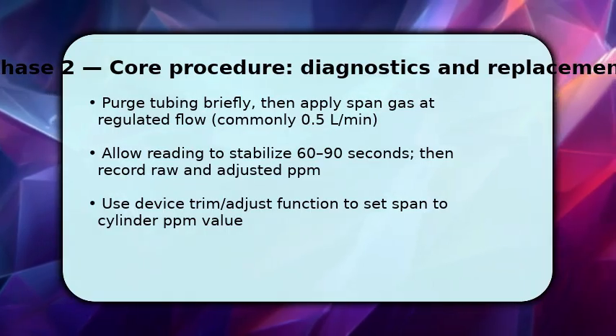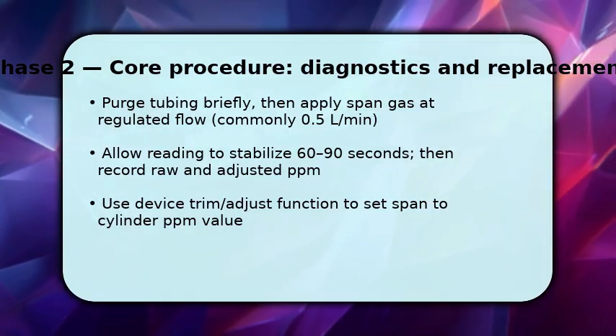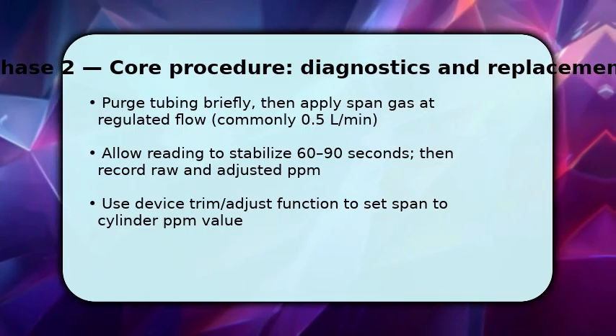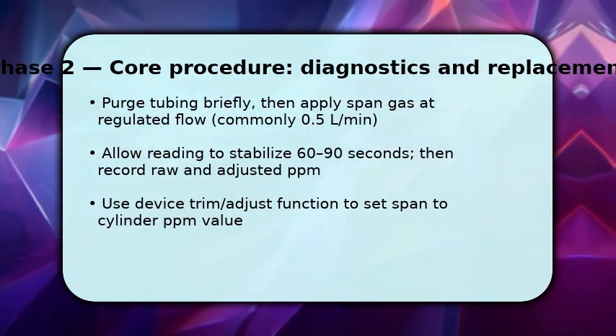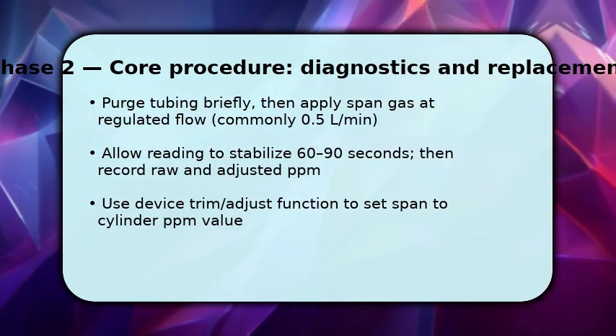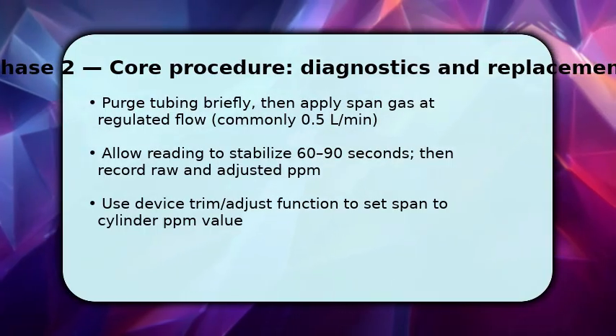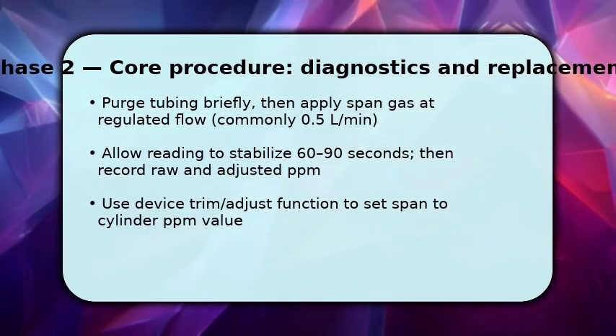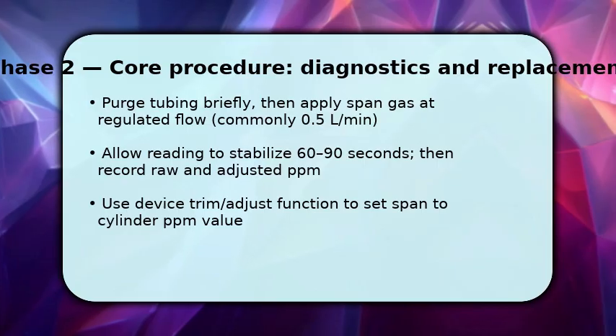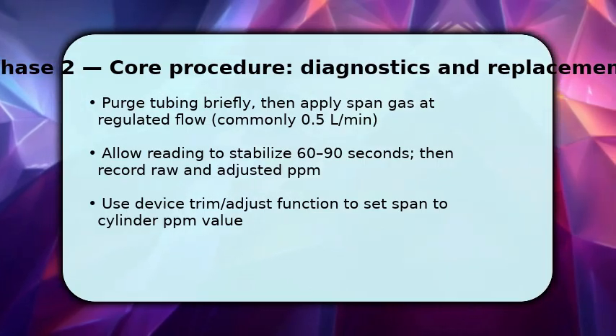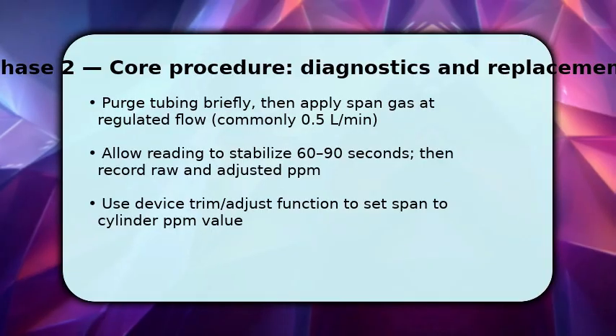Open the regulator to a steady 0.5L/min and place the tubing on the sensor inlet. Wait for the display to stabilize, typically 60 to 90 seconds, because the sensor needs time to respond. Once stable, compare the reading to the cylinder ppm. Use the device's span adjustment or trim control to match the exact ppm value.